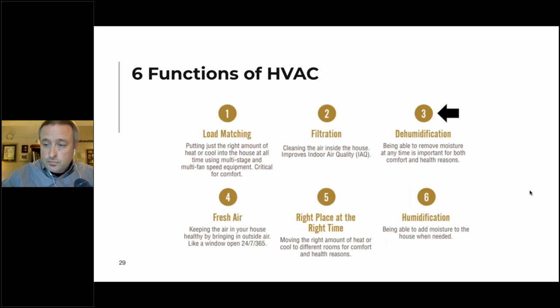A quick question. On existing homes especially, I assume if you get thicker filter boxes, are those going to have less of that resistant airflow problem that you mentioned versus the thinner ones? In fact, I'm going to show numbers in a slide later. Okay. Yeah, that's a good question. You have to run 4 and 5 inch or 6 inch media filters to get the resistance low. I just tested one yesterday where the filter by itself was creating 0.7 inches of water column of back pressure, and the whole system isn't supposed to be over 0.5. The filter alone was creating more than that. That system, it was noisy, and he's going to be replacing his fan motor soon with that kind of pressure. So yeah, it's important.